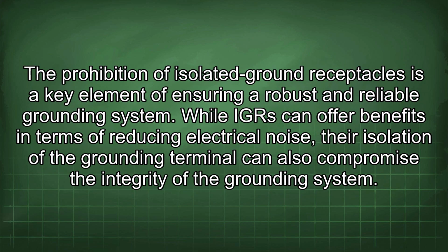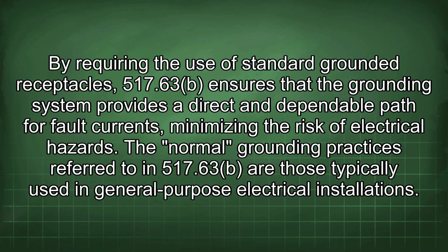injuries. The prohibition of isolated ground receptacles is a key element of ensuring a robust and reliable grounding system. While IGR can offer benefits in terms of reducing electrical noise, their isolation of the grounding terminal can also compromise the integrity of the grounding system.